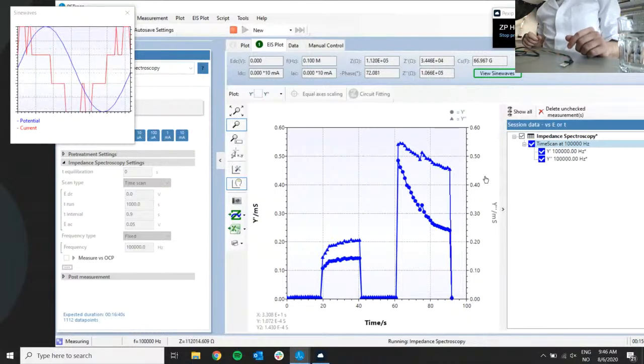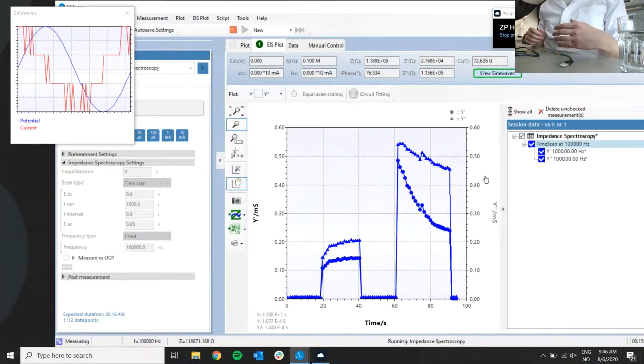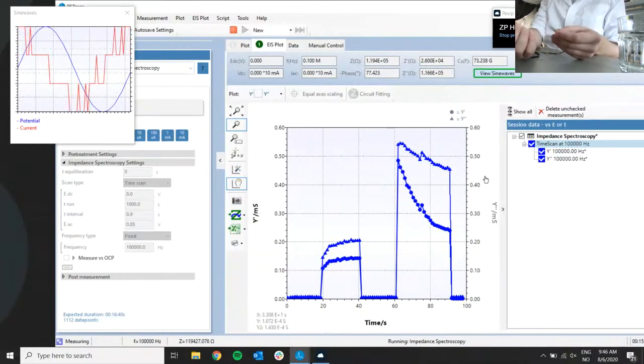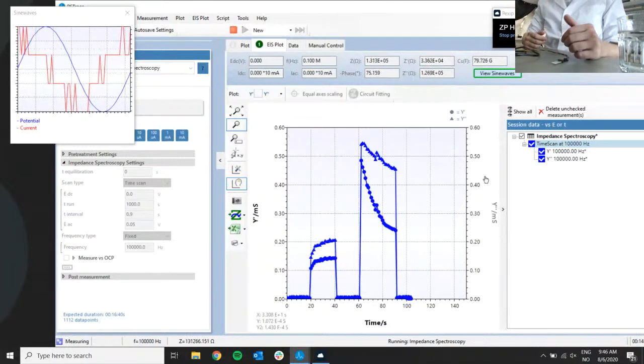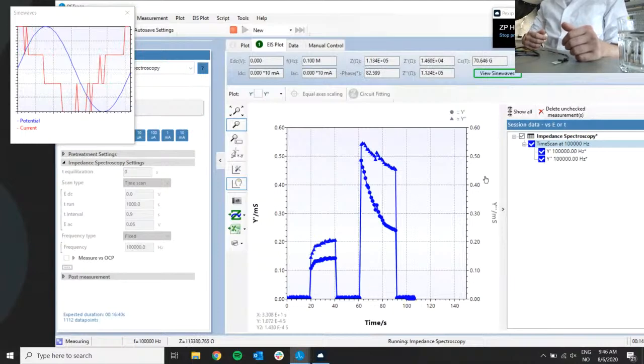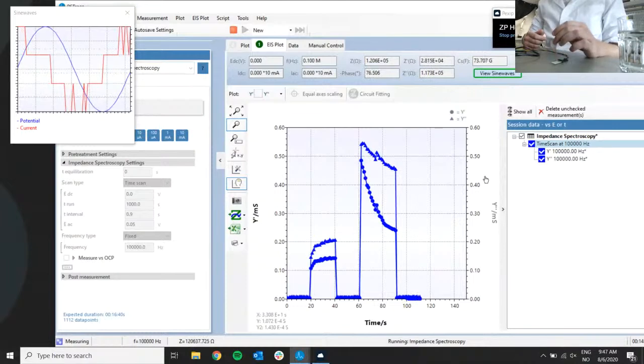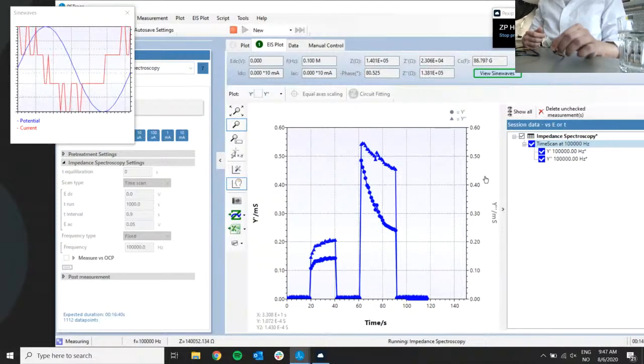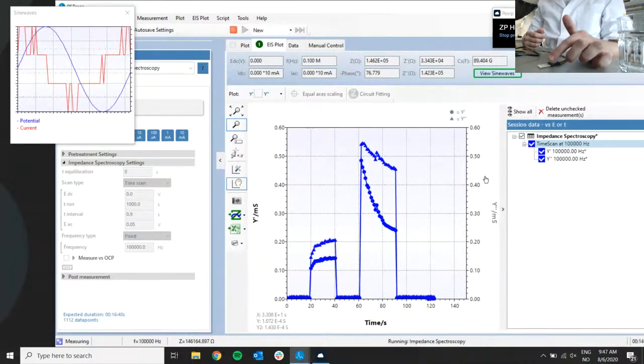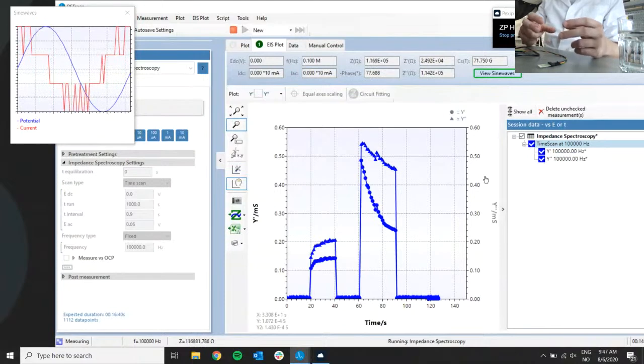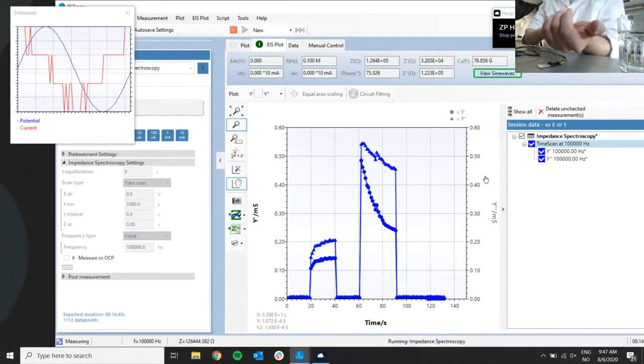This was a quick demo on how to do skin-type measurements. You can measure on many different locations like the palm of your hand or other locations with high amounts of eccrine sweat glands. If you're trying to measure on body parts with lower amounts of sweat glands, you might need a contact gel to get a good sensor contact with your skin. The electrodes are flat in this case, which is why we can do these measurements — traditional conductivity electrodes that Martin mentioned have a parallel plate, so it's very difficult to do a surface measurement.